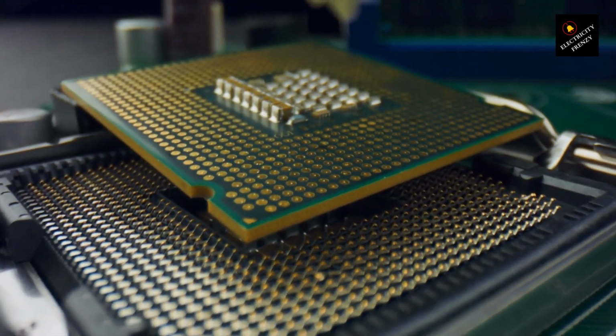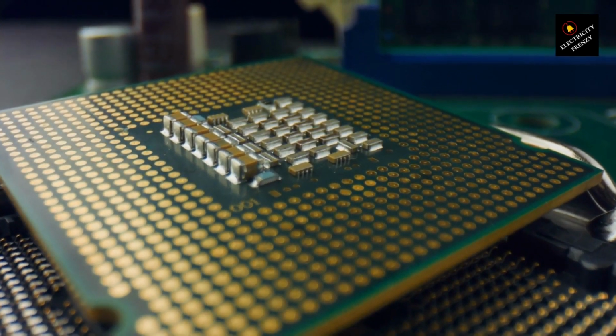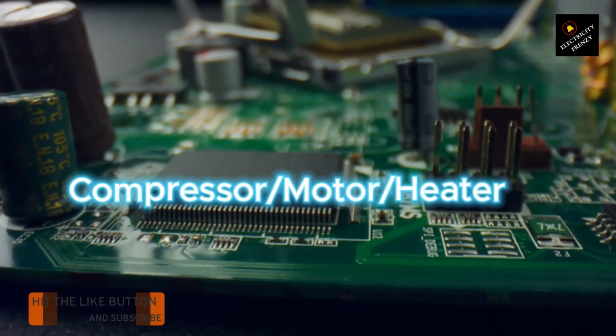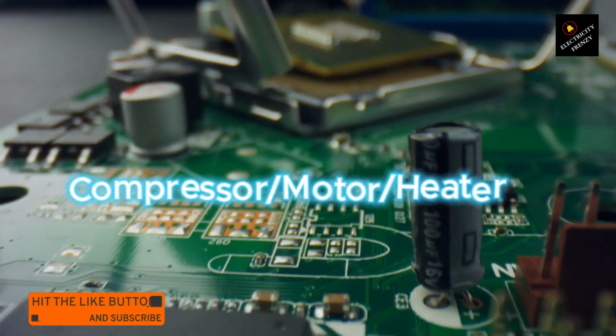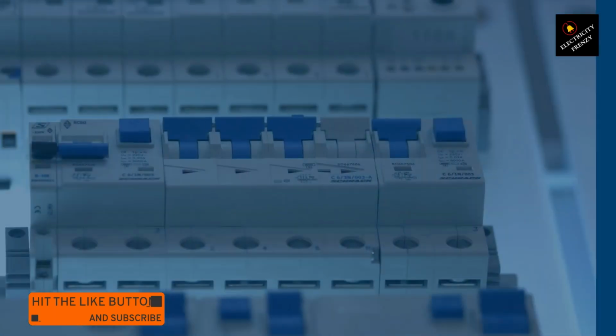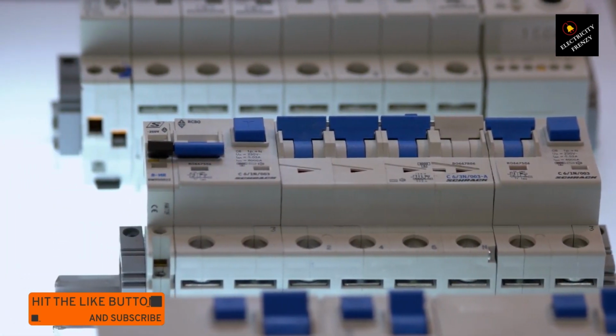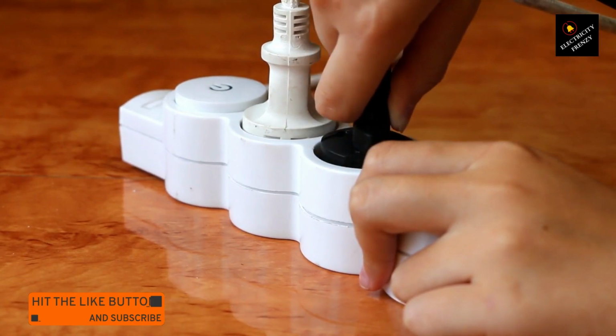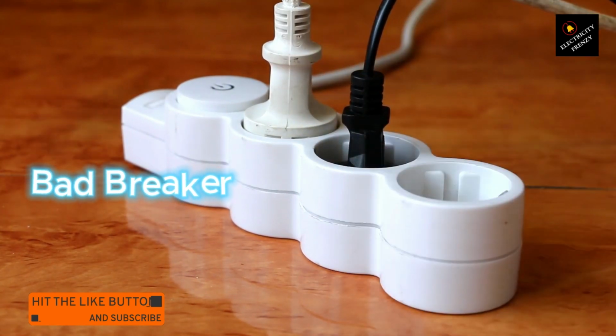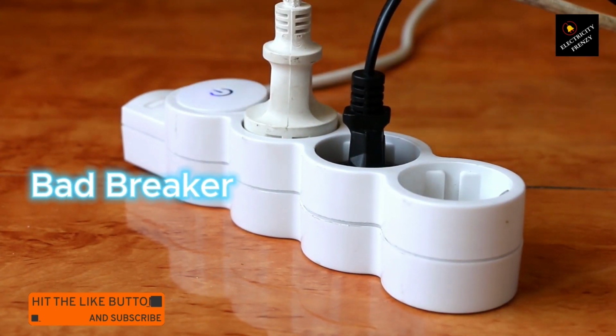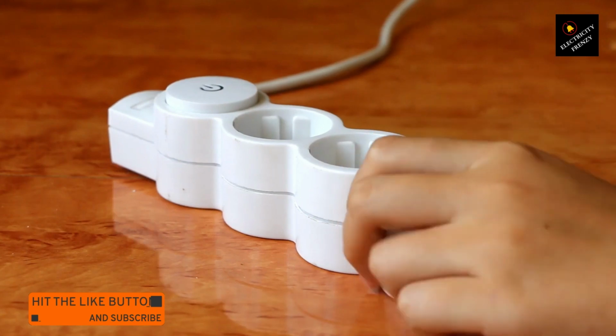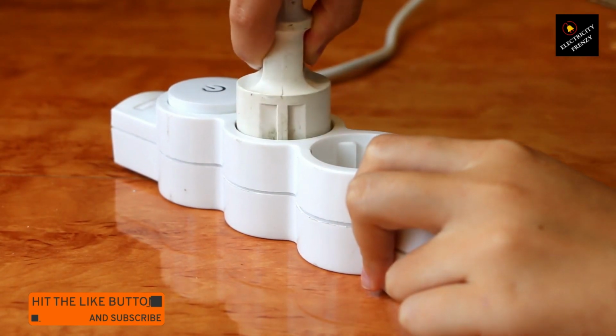Defective components. The refrigerator itself may have a faulty component, such as a compressor or motor, which is drawing too much power or causing a short circuit. This can result in the breaker tripping as a safety measure. Breaker malfunction. In some cases, the circuit breaker itself may be faulty or worn out, causing it to trip more easily than it should. If the breaker is old or damaged, it may need to be replaced.